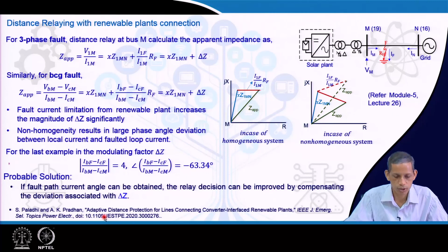Then what are the probable solutions? If the fault path current angle can be obtained, like we saw in the fault classification perspective, the relay performance can be improved by compensating the deviation associated with delta Z. This reference reveals such an approach to mitigate the issue of distance relay performance in the presence of renewable resources.